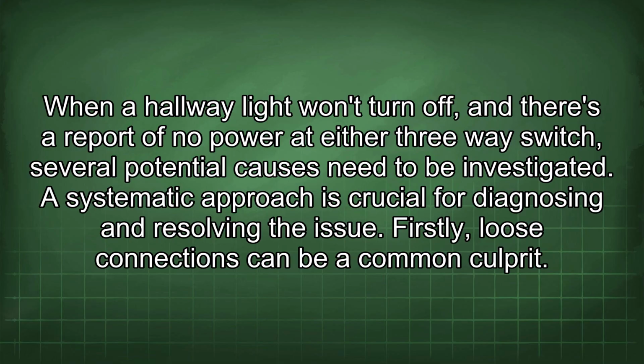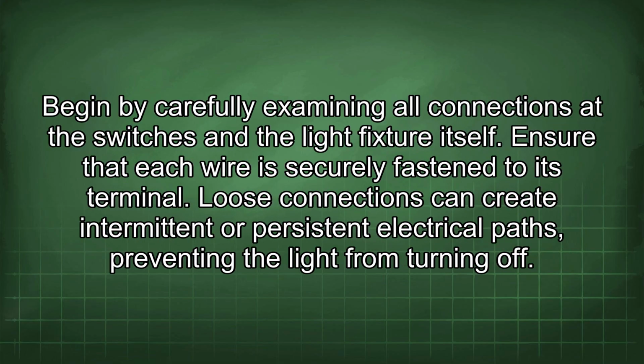Firstly, loose connections can be a common culprit. Begin by carefully examining all connections at the switches and the light fixture itself. Ensure that each wire is securely fastened to its terminal. Loose connections can create intermittent or persistent electrical paths, preventing the light from turning off.